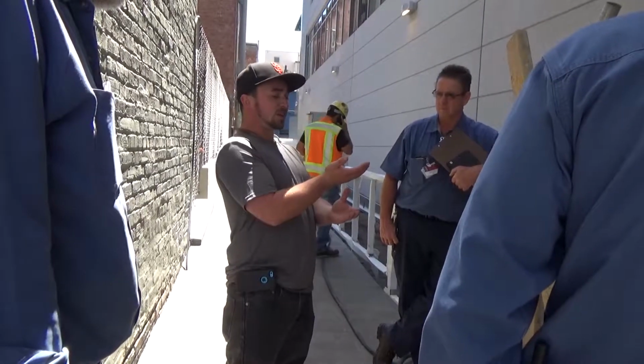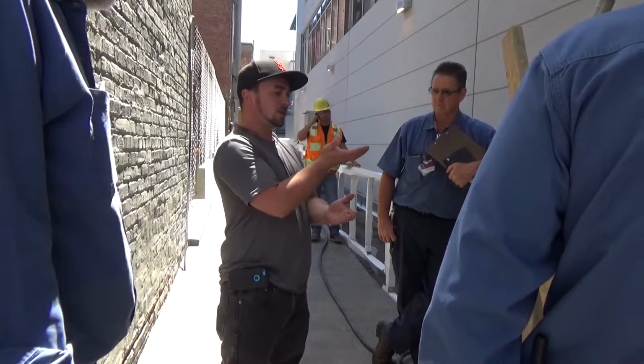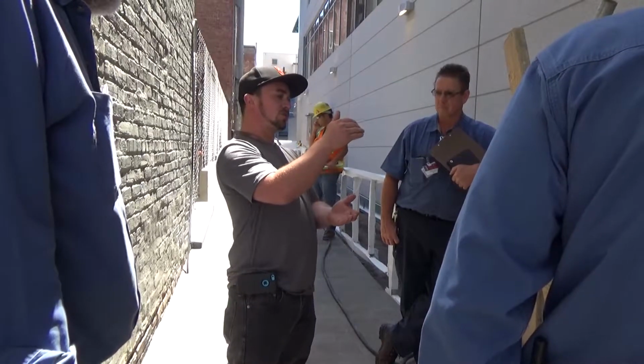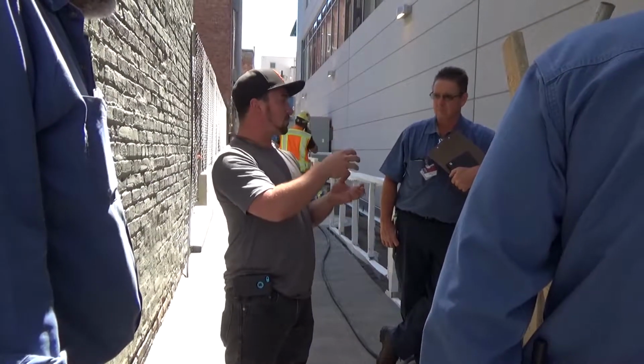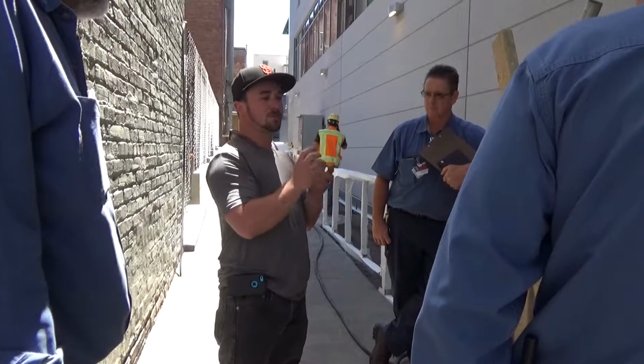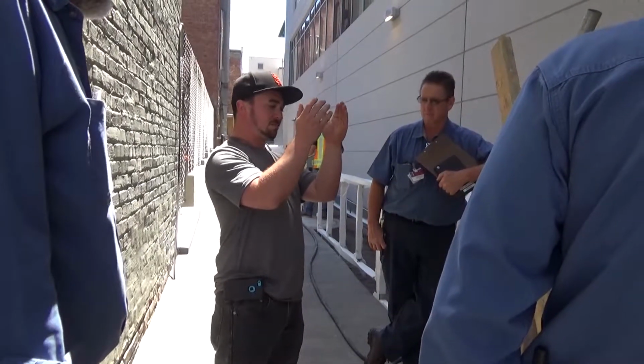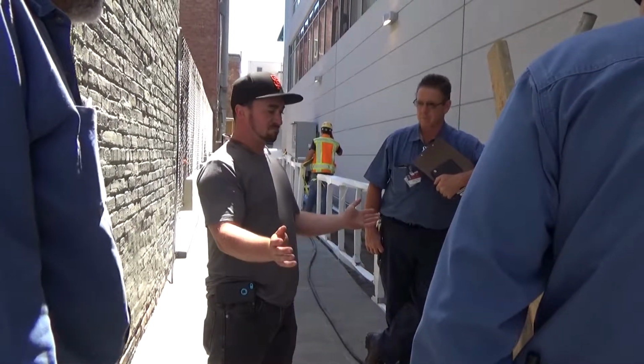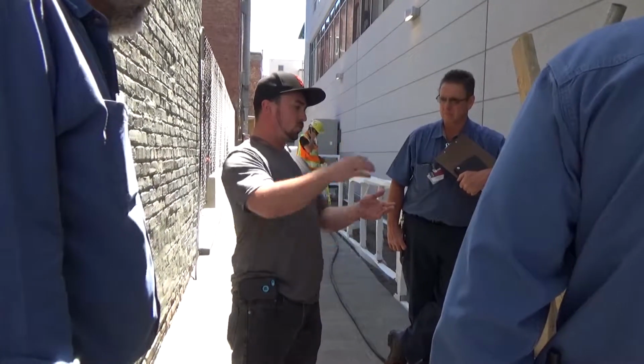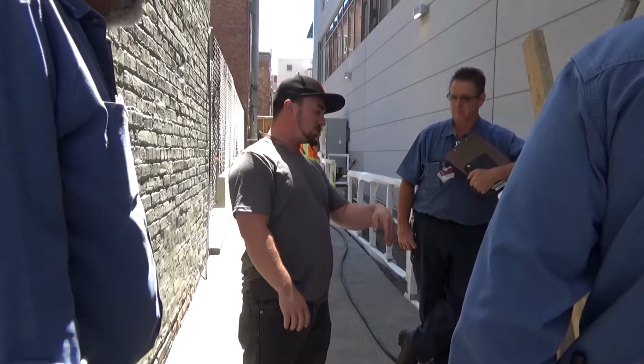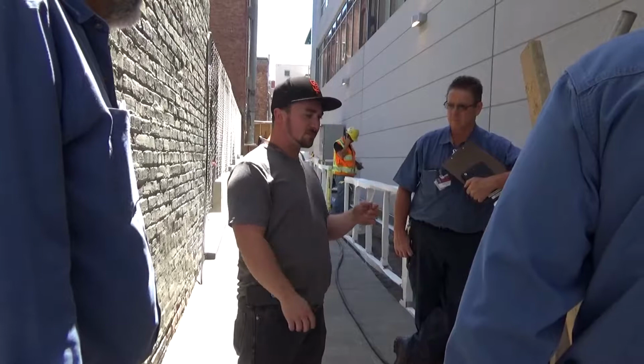Say the pit keeps filling up and pump 1 can't handle it. Water keeps rising, and the third float from the bottom makes, and that second pump is going to come on. So both pumps are going to be pumping it down. Hopefully they can pump everything down and the pit gets empty, and the pumps will keep going all the way till that bottom float breaks, and then everything shuts off.